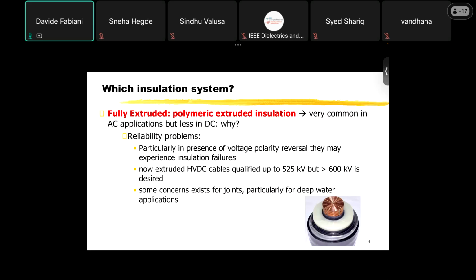Okay, so the reason for that, the fact that they were not so common for HVDC, is that polymeric insulation had some reliability problems if fed by DC. In particular, these problems came when we had voltage polarity reversal. And this can occur under HVDC if you want to reverse the power. Sometimes you have polarity reversal, and this can create insulation failures.